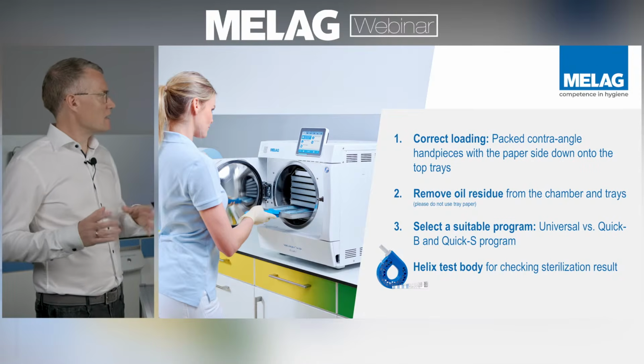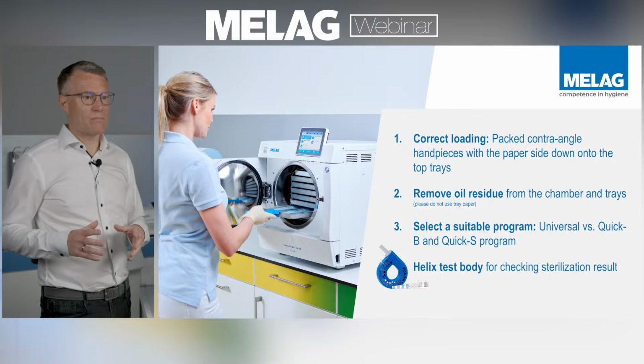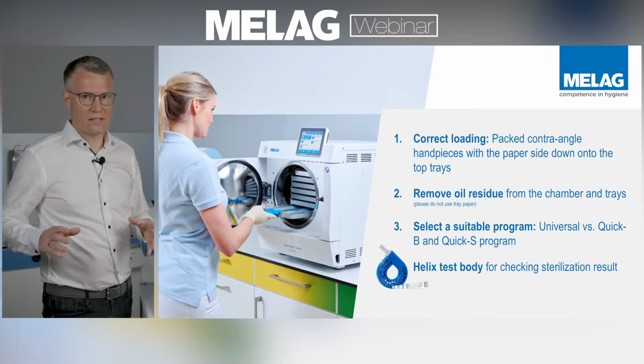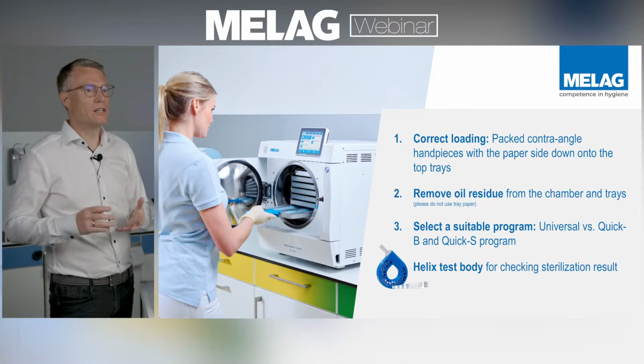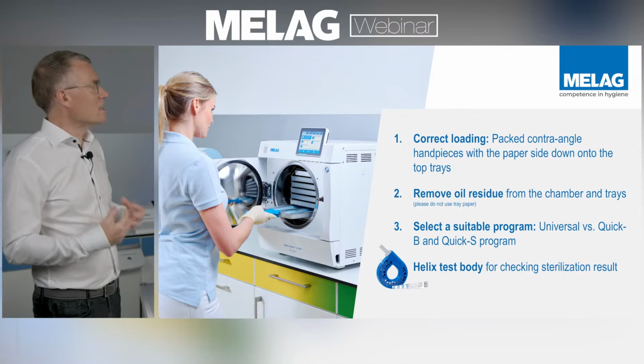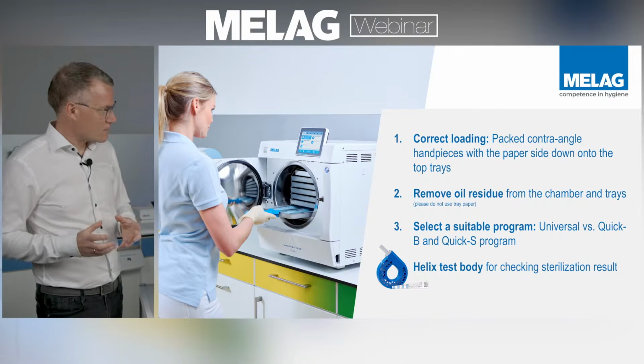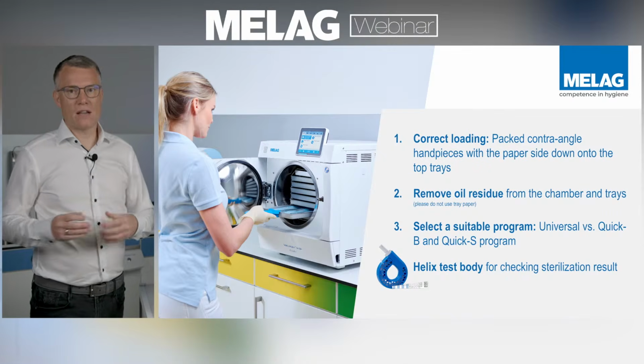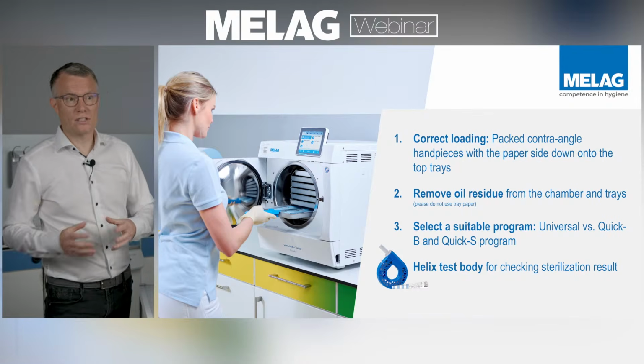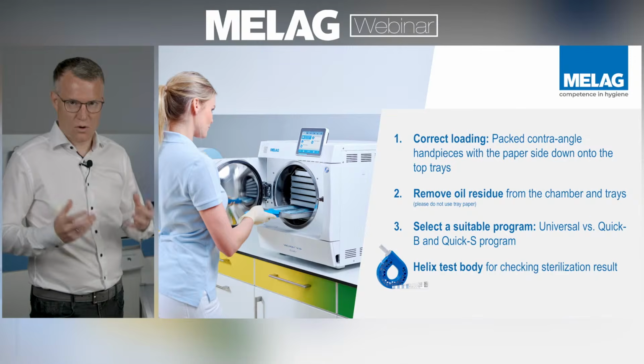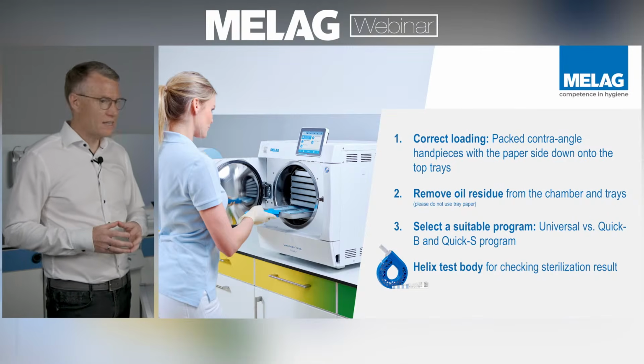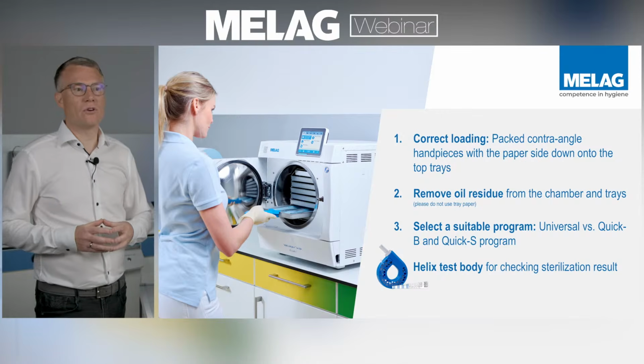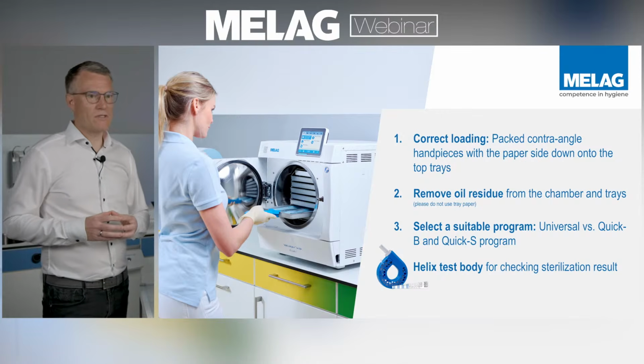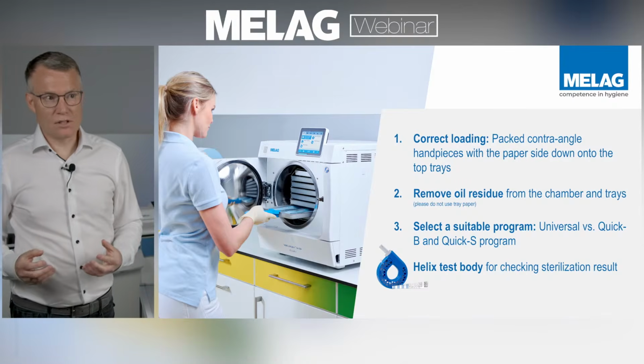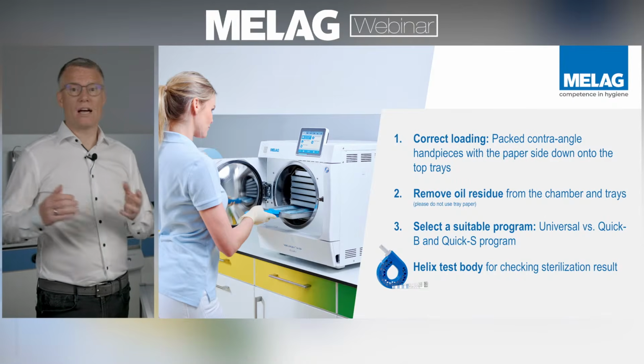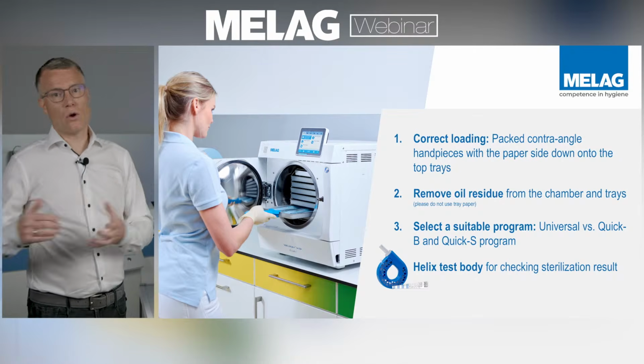If you see any remaining dirt or oil in the chamber, please make sure that you get rid of all this dirt and remaining oil, because the oil should be on or inside the instrument, but not in the sterilization chamber. So there are several products and solutions available to get rid of those spots, dirt or oil, for example, chamber protect. So there should never be any dirt or oil remaining in the chamber of the sterilizer.